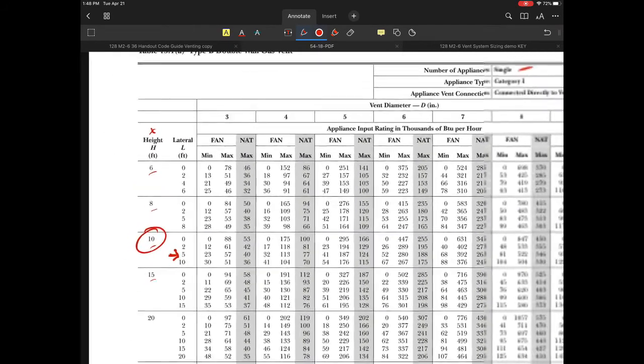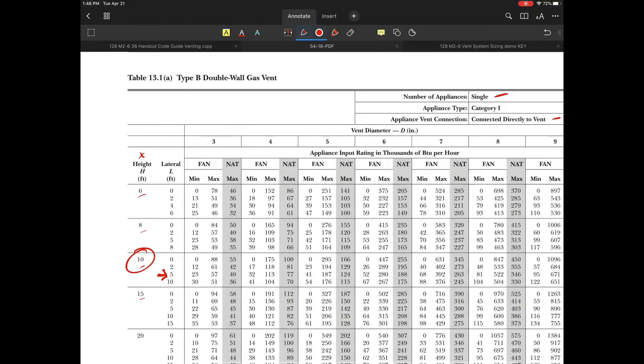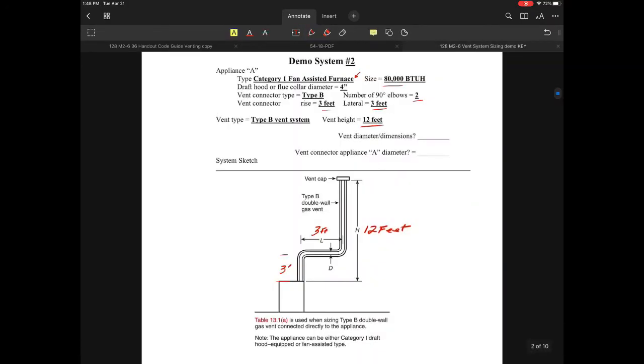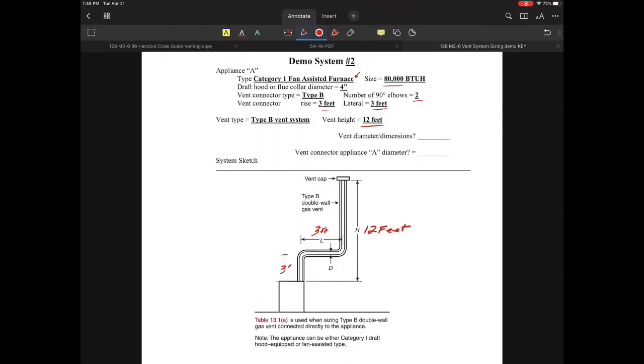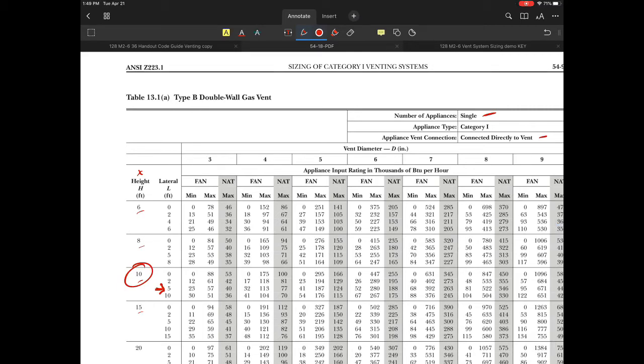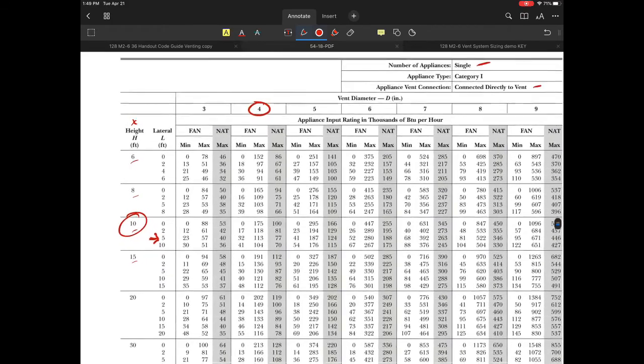The other thing to identify is the connector size. In this case, we have a four-inch connector with 80,000 BTU. Looking at the table, four inches is what we'll start with.